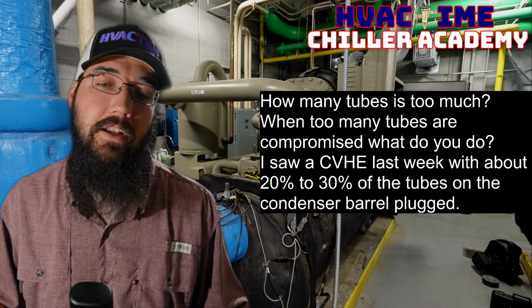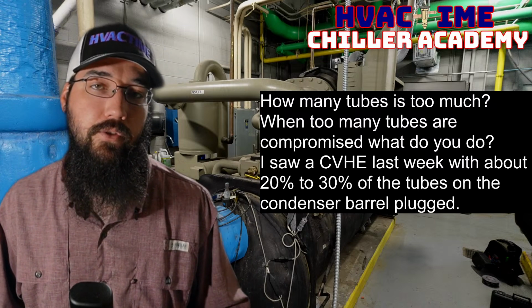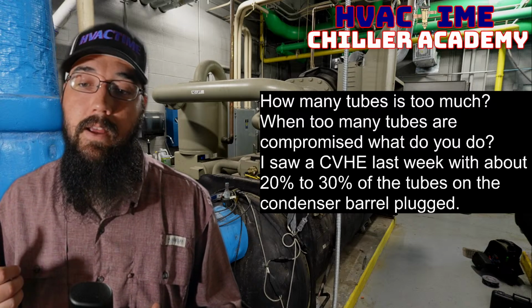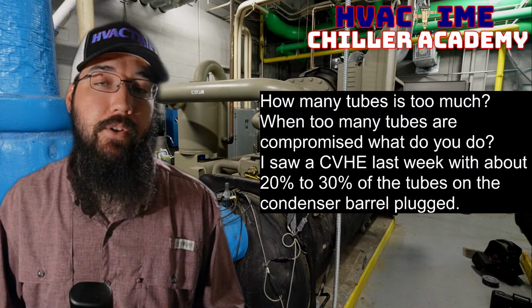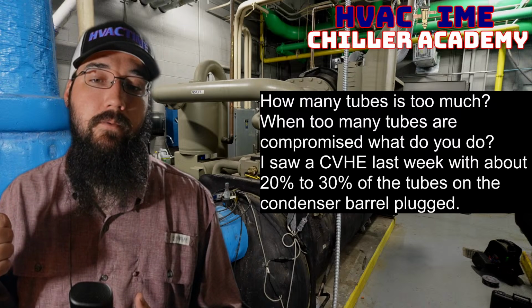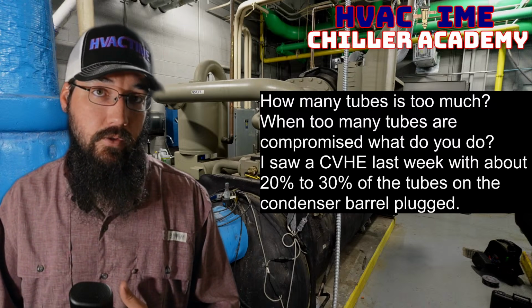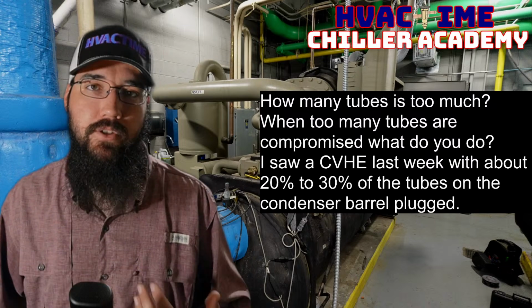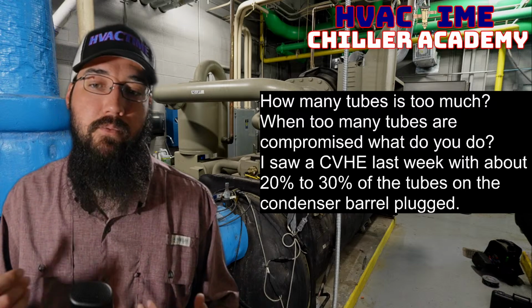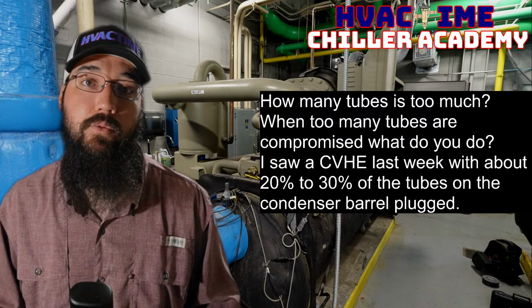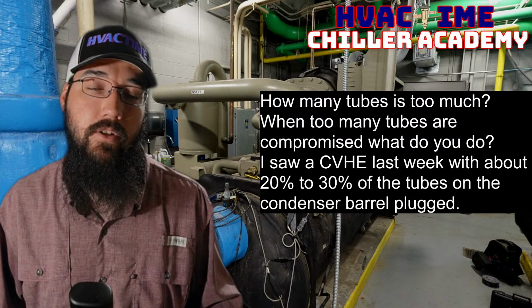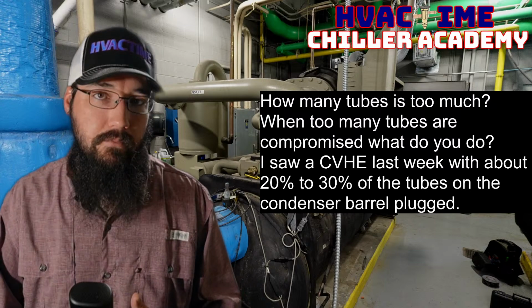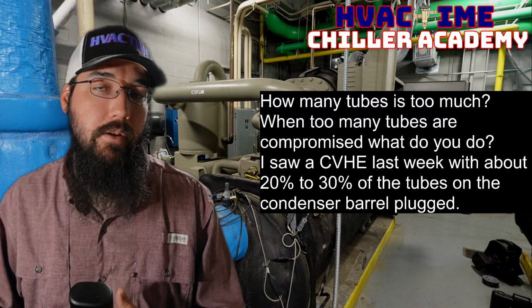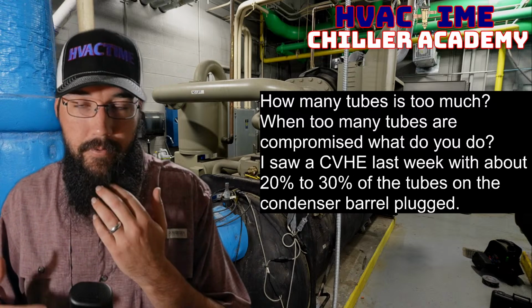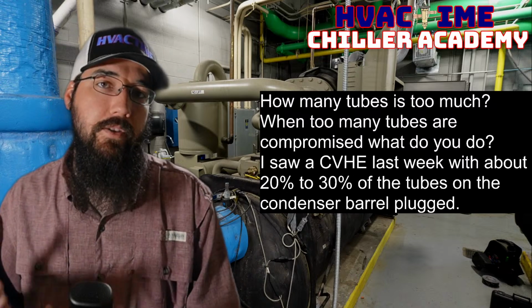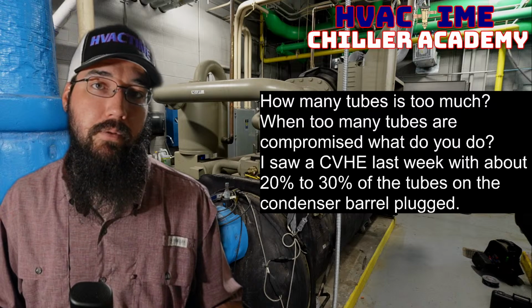So in your particular case, with 20 to 30% of the tubes being plugged, yeah, I would expect that machine to run pretty significant condenser approaches, and brushing the tubes isn't going to fix that. That may be why you're in there trying to brush the tubes. You may have had higher approach. You may have been struggling with high head pressure. The default there is, okay, well, maybe our tubes are plugged up or dirty otherwise. So you go in there to brush them, but then you see a whole bunch of them are plugged, right?